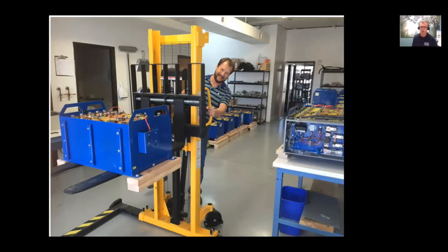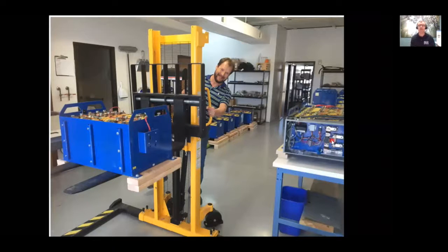Unlike a lead acid or nickel iron battery, which is essentially just cabling and connections, the lithium, or specifically lithium iron phosphate chemistry we work with, requires a complex battery management system. Let me turn on my highlighter here so I can show you. In this enclosure, you can see some of the electronics for the battery management system, including the BMS, power supply, relays, and a sealed contactor that allows us to protect the battery by opening the circuit potentially under load. That's what this device allows us to do. So if someone were to potentially overcharge or over-discharge a battery, we now have safety mechanisms built right onto the battery to preserve its life and allow it to keep working for years to come.